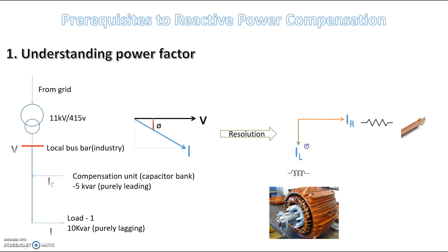We have to closely watch that we compensate the reactive component. Look, we cannot reduce the reactive component because if I have the requirement, I'll have to augment, I'll have to buy new motors, enter it in the plant, synchronize it to the grid and start feeding it. So it is inevitable. IL cannot be reduced. But what I can do is, I can connect a capacitor, I can connect a capacitive element that is going to supply the lagging current to the bus bar.